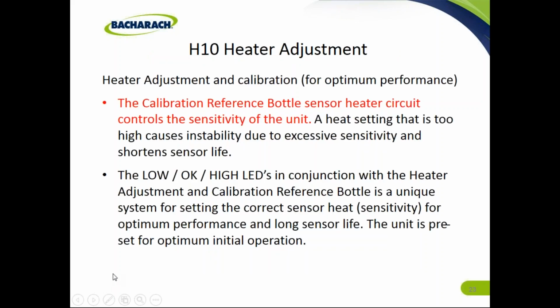H10 heater adjustment. H10 adjustment and calibration for optimum performance. The calibration reference bottle sensor heater circuit controls the sensitivity of the unit. A heat setting that is too high causes instability due to excessive sensitivity and shortened sensor life. The low, OK, high LEDs in conjunction with the heater adjustment and calibration reference bottle is a unique system for setting the correct sensor heat sensitivity for optimum performance and long sensor life. The unit is preset for optimum initial operation.